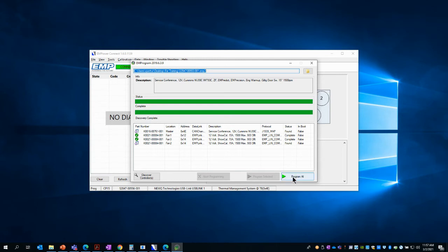Once I select Program All, in this situation, we will look to have the master controller and fan number 2 controllers recalibrated and hopefully their status moved from found to complete. At this point, if your status shows anything other than found or complete, you would want to take a screenshot to send to your EMP representative.